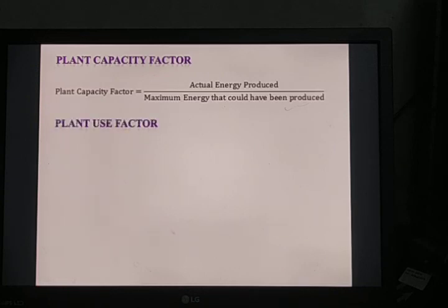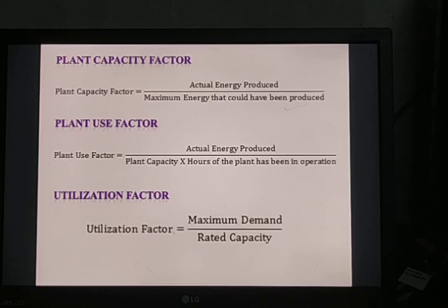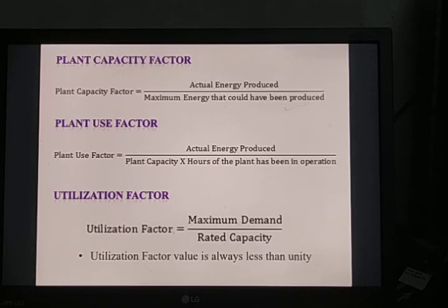Plant use factor is defined as the ratio of actual energy produced to the product of plant capacity and the number of hours for which the plant was in operation. Utilization factor is defined as the ratio of maximum demand to the rated capacity of the power plant, and its value is always less than unity. For example, with a demand of 350 megawatt and a plant capacity of 470 megawatt, the utilization factor is 350 divided by 470, which equals 0.745 — always less than unity.